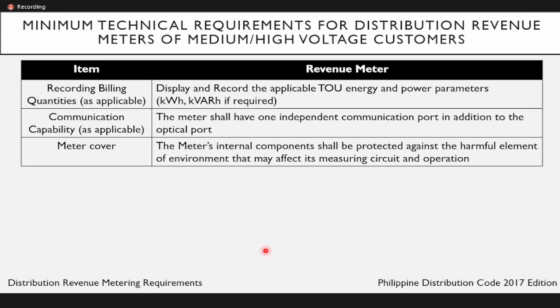For the recording of billing quantities, as applicable, the revenue meter should display and record the applicable time of use energy and power requirements, either the kilowatt hour or kilovolt ampere reactive hour, if required. The communication capability, as applicable, should at least have one independent communication port in addition to the optical port. For the meter cover, the meter's internal components shall be protected against the harmful elements of the environment that may affect its measuring circuit and operation. All this that I mentioned to you is based on the distribution revenue metering requirements from the Philippine Distribution Code 2017 edition.